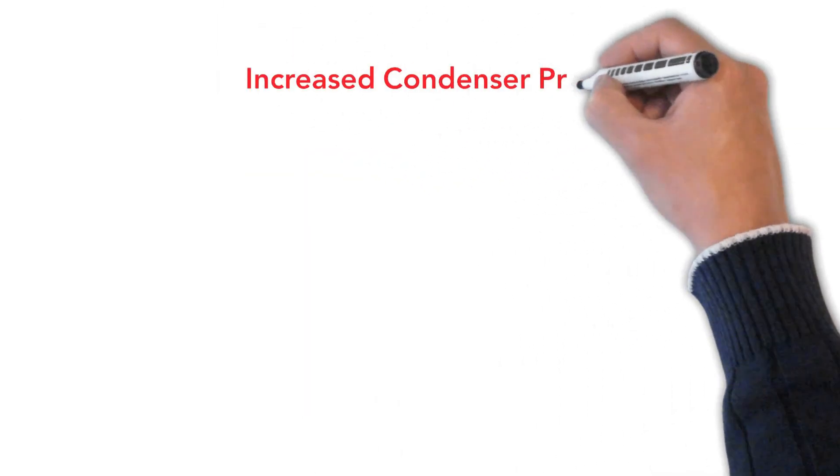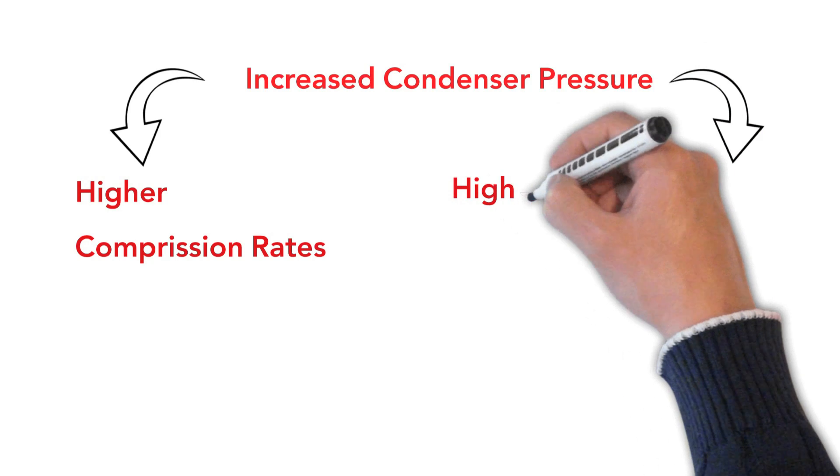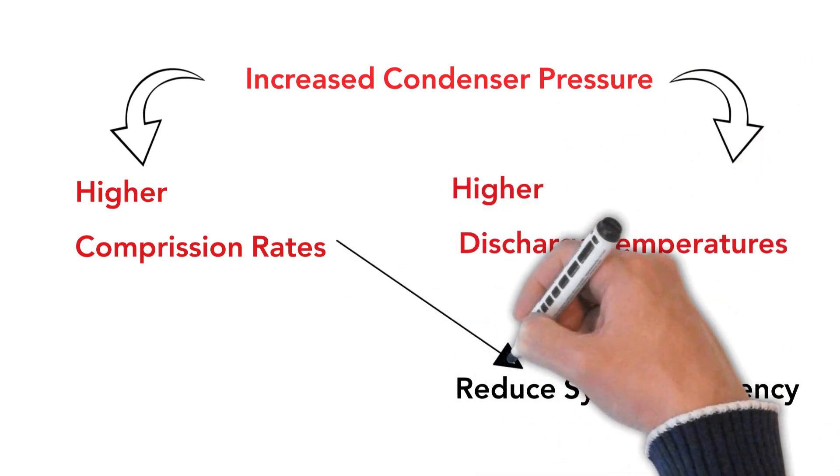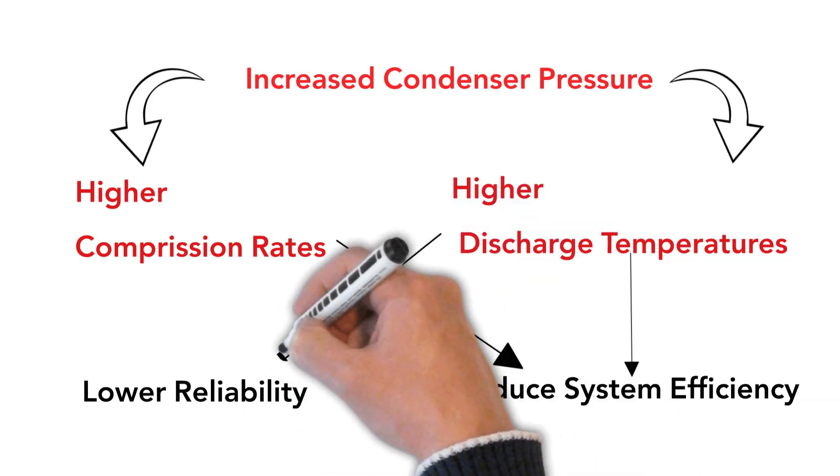Increasing condensing pressure leads to higher compression ratios and higher discharge temperatures, both of which reduce system efficiency and can lead to lower reliability.